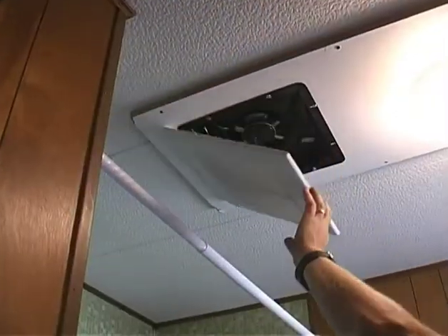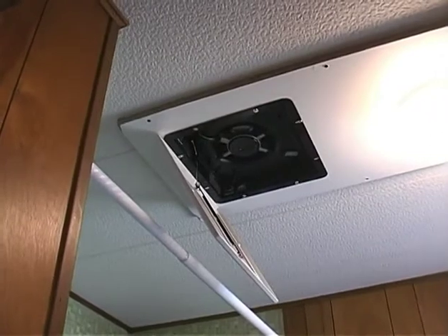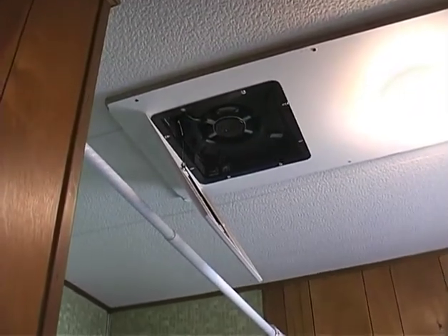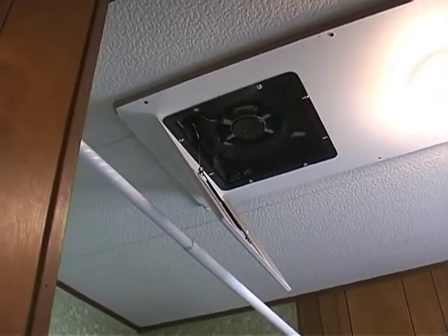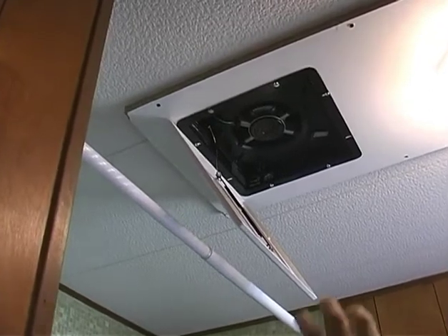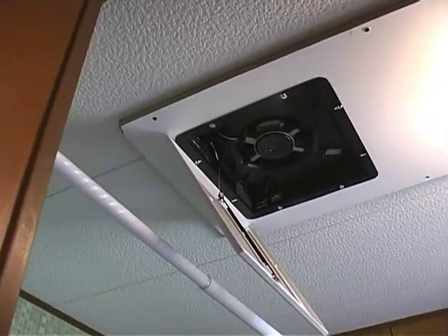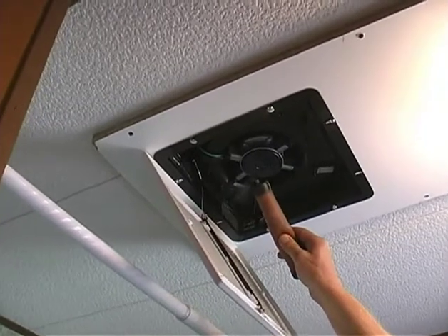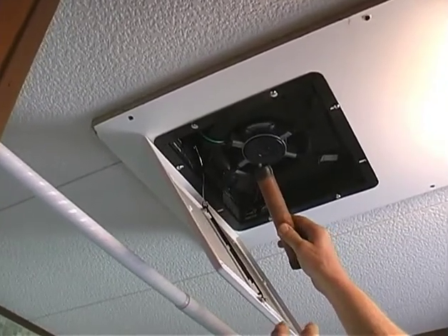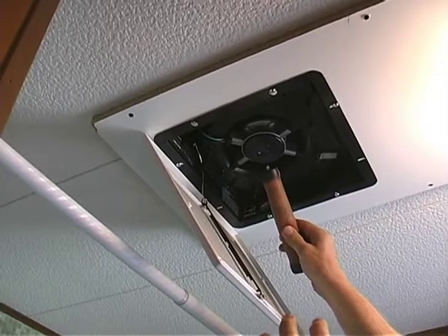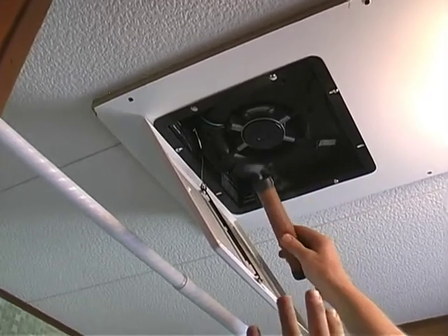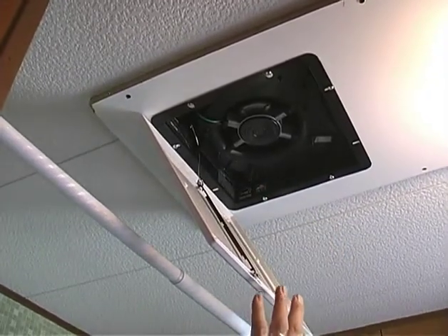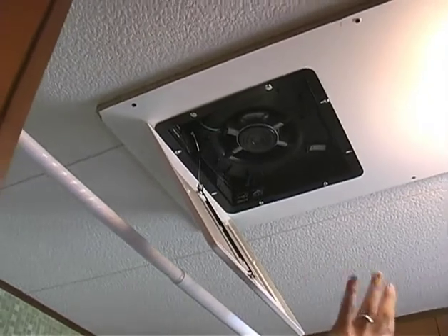We're going to go ahead and look at the bath fan, which is another suspected air leakage site in this home. I'm going to use the airflow indicator. We are pulling air in with the blower door at this moment, and it's obvious that air is moving through this fan. There's probably no damper on the fan, so air will leak in during the blower door test and out when the blower door fan is off.